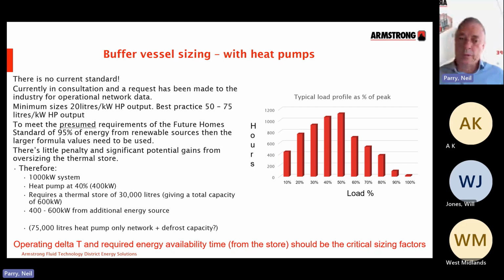But if we use one of the more simple formulas here, you can see that for a 1,000 kilowatt system, you can size the heat pumps at 40%. That's going to give you, because of this demand profile or runtime profile, around about 90 to 95% of the time the energy is going to come from your low LZC sources. So it'll give you a thermal store size of around 30,000 litres, giving you a total capacity of around 600 kilowatts, and then you can divide the remaining difference up, so that 400 to 600 kilowatts from an additional energy source. So this is if it's a hybrid system. Now that additional energy source could be gas boilers, it could be electric boilers. It doesn't really matter, really.